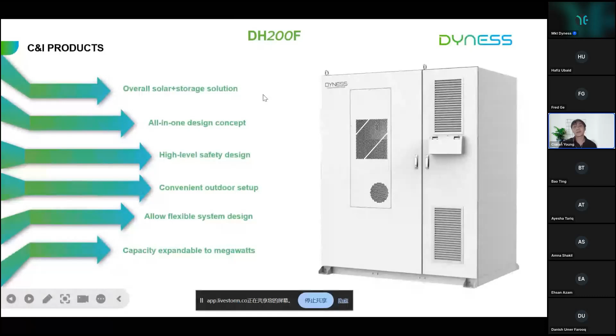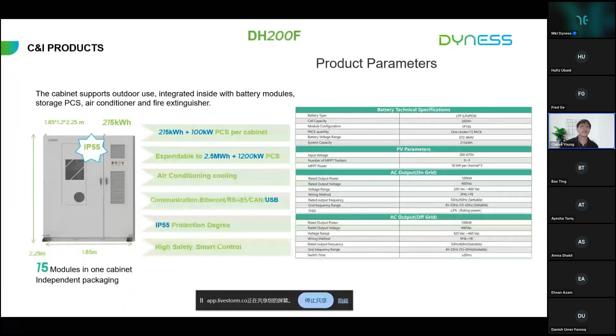Let's check the specification. It works with the 280 ampere-hour battery cell at 0.5C. Inside there can be a maximum of 15 packs of battery. This solution works at 400 volts voltage stage because we consider more about convenience and safety. Inside there is an AC unit and fire extinguishers.